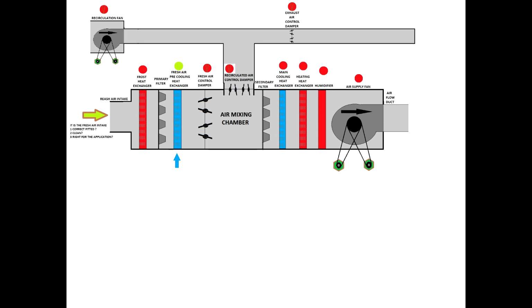If that is green and it's okay, there's no blockage, you start checking the dampers and the heat exchangers one by one. You check the actuators to see if they're okay. You check if enough fluid goes through the heat exchangers so you will not have any blockage. And you do this for all heat exchangers, for all actuators. You check the VSDs and the motors. And once you finish this, you'll connect everything to the PLC. You can connect this before to the PLC and check them through the PLC if you want.